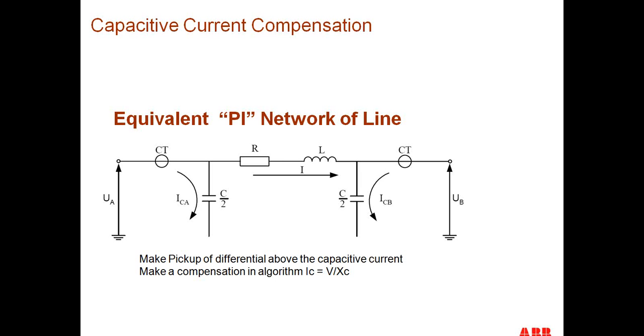What modern relays do now is that, under steady state conditions, meaning I energize the line and the breaker's closed for a period of 500 milliseconds, we can measure that line charging current and subtract it from our differential current. So our new level of differential current doesn't have the charging current component anymore, which means we don't have to allow for the line charging current when we set our minimum differential operating characteristic for the minimum operating point for the line. So we're already compensating for this charging current.